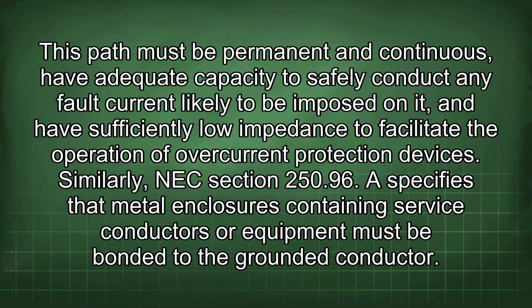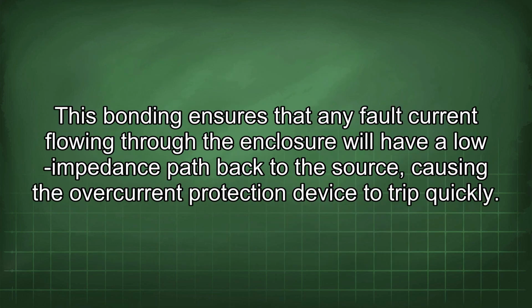Similarly, NEC Section 250.96 specifies that metal enclosures containing service conductors or equipment must be bonded to the grounded conductor. This bonding ensures that any fault current flowing through the enclosure will have a low impedance path back to the source, causing the overcurrent protection device to trip quickly.